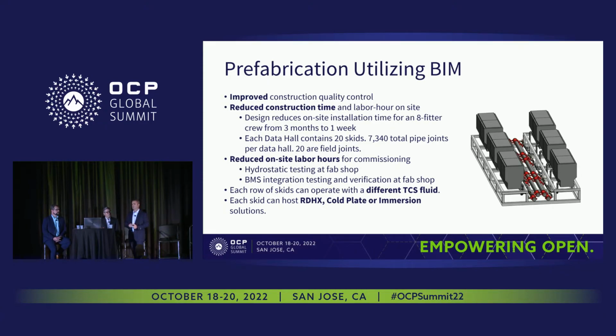Now we're not just doing that on the data halls, we're also doing it in the mechanical galleries where our CDUs exist. In a typical data hall, we have space for 120 immersion tanks that are 48 OU. If you go through all the variations and requirements for connecting 120 immersion tanks in that type of environment, you have approximately 7,340 pipe joints in a single 10 megawatt data hall.